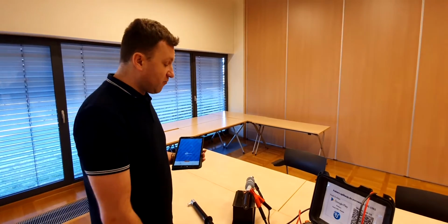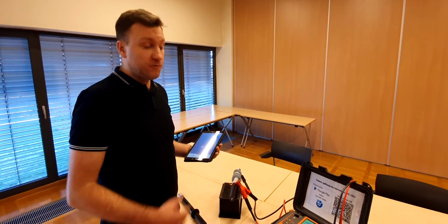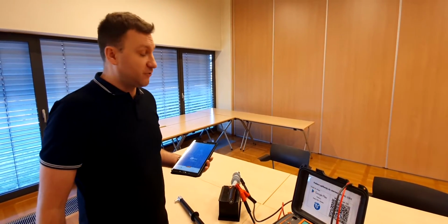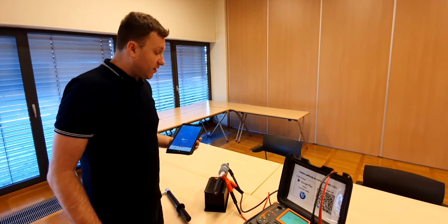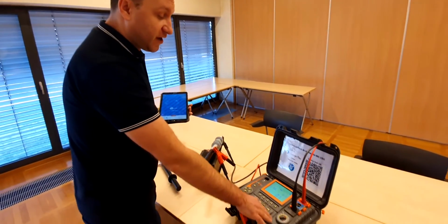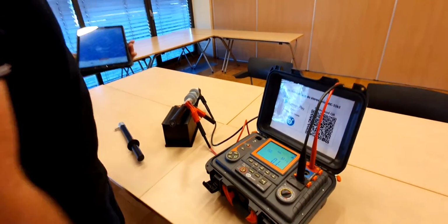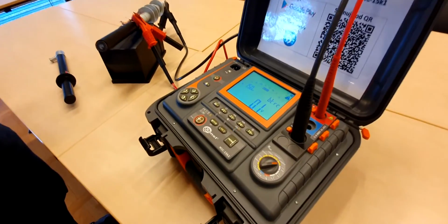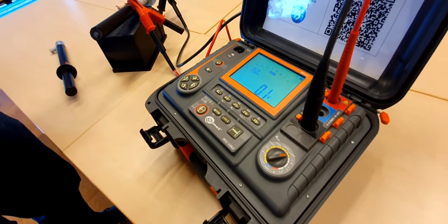Now, let's look at the second situation. So, what will happen when we have a short in a cable? What will the meter display to us? To simulate these conditions, I have increased the test voltage to 15,000 volts and test current to 7 milliamps.